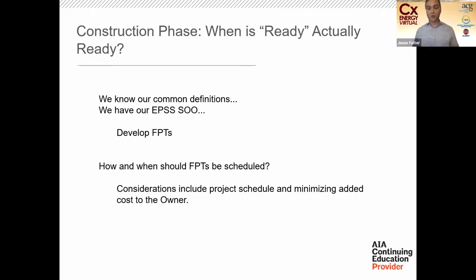The goal, this value add from design into construction, is to document not only design intent, but before that, what is the owner's expectations. We want to develop a commissioning plan, a means for functional testing a system, that reflects how the owner would operate it. This logic, this philosophy, is reiterated throughout ACG and really the commissioning approach. We're talking about emergency power systems today, but know that this approach can be applied to others.